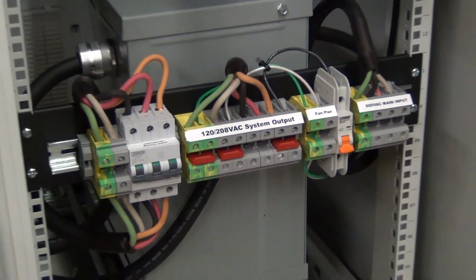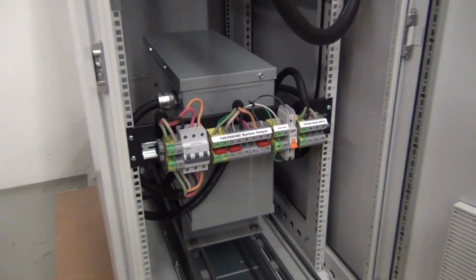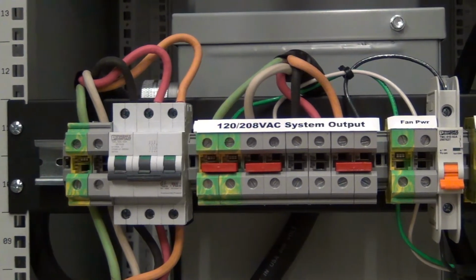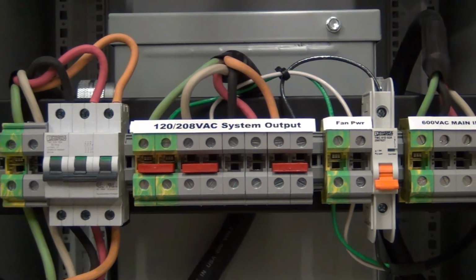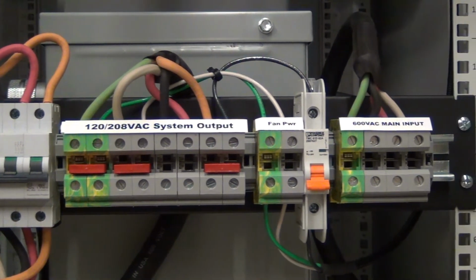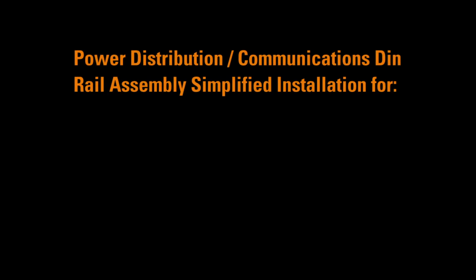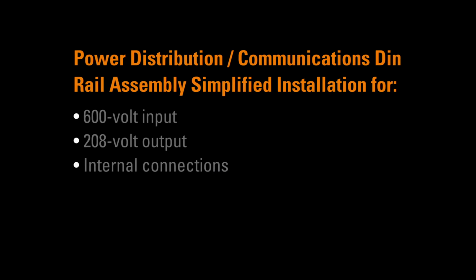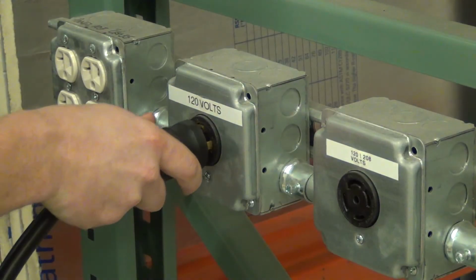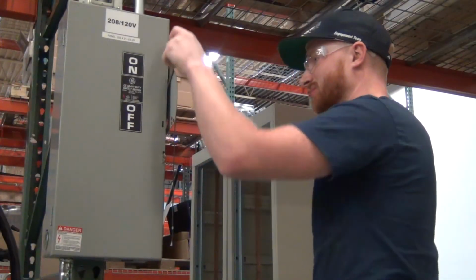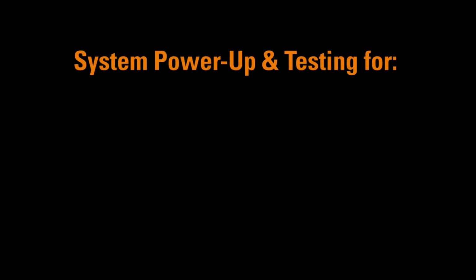Power distribution and communications DIN rails were assembled using correctly sized circuit breakers, terminal blocks, cut-to-length cable, and connectors to provide all of the intra-cabinet equipment connections. These steps facilitated ease of installation at the user site for the 600-volt input and 208-volt output, as well as all internal connections.